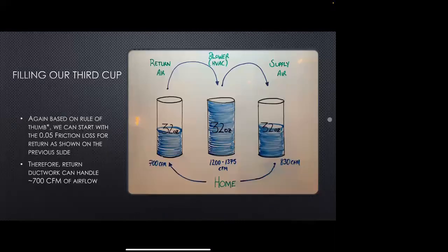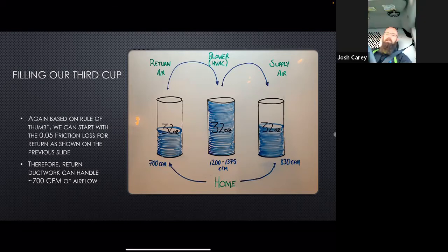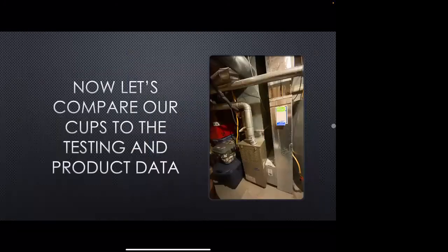Now, how much does it slow down? Do you know? Does anybody? 130. Slows down by 130? Depends on the static. Yes. Depends on the static. Okay. So that's when we need more data. So now let's compare our testing and the product data of the furnace.